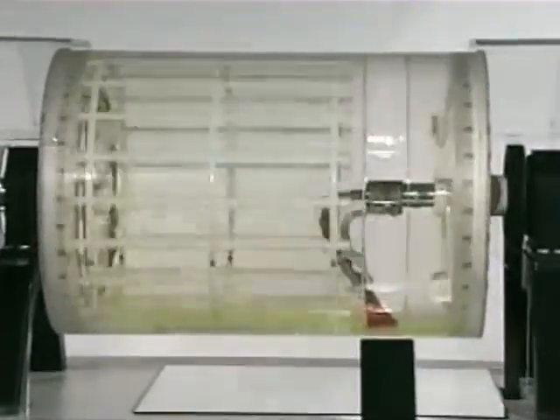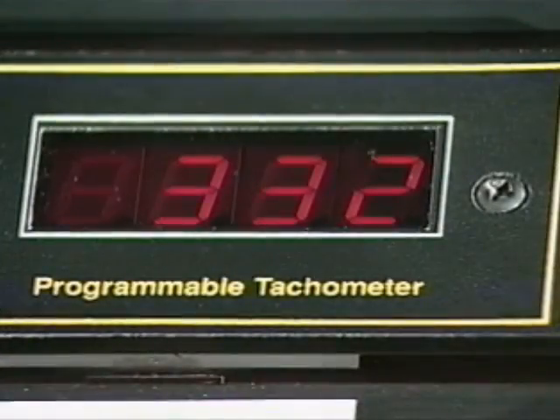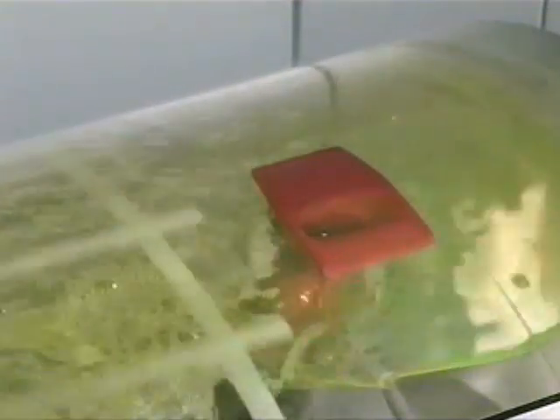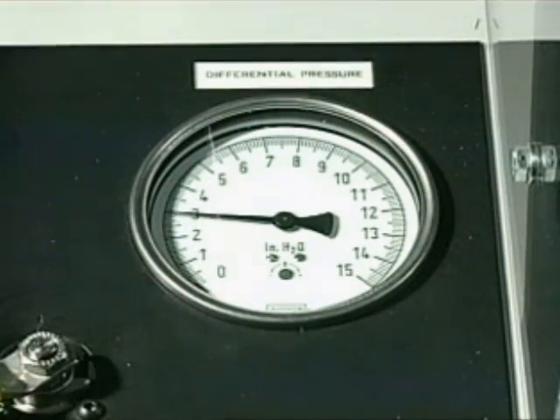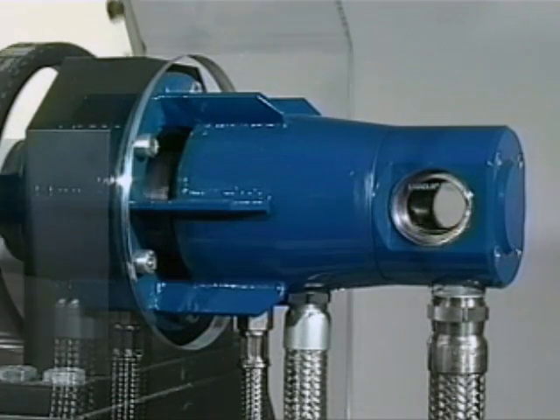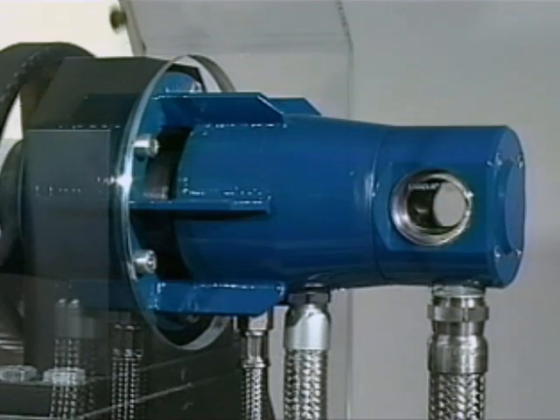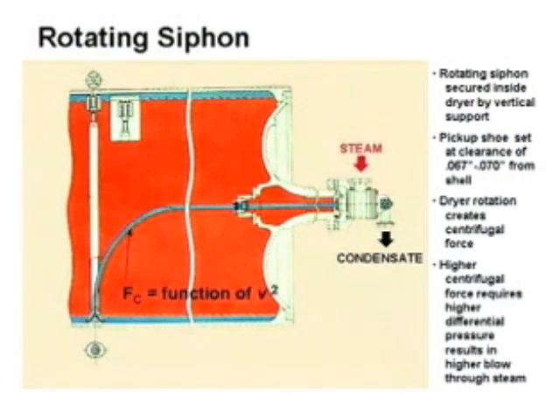With speeds less than 330 feet per minute, the condensate is at a puddle condition. With a stationary siphon, the pickup shoe is dipped into the puddle of condensate. The differential pressure of the drum is set to the equivalent of 3 inches of water column, and the condensate continues to be discharged with minimal blow-through steam. In the case of the rotating siphon, the siphon continuously rotates, with the dryer only momentarily being dipped into the puddle of condensate, picking up a minimal amount of condensate and an increased amount of steam. Excessive blow-through can lead to steam and condensate system problems.